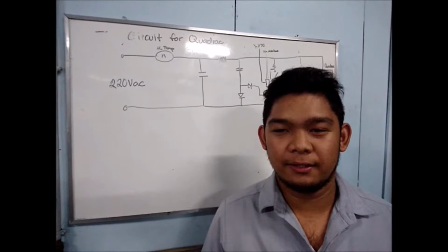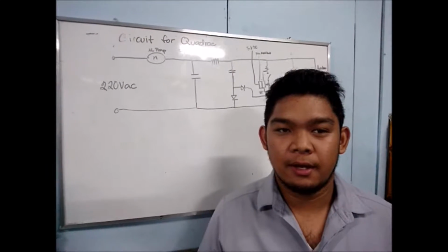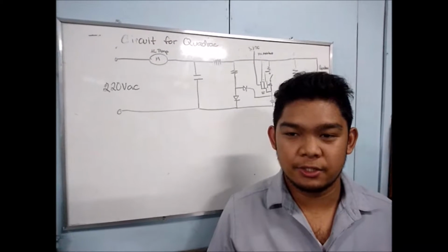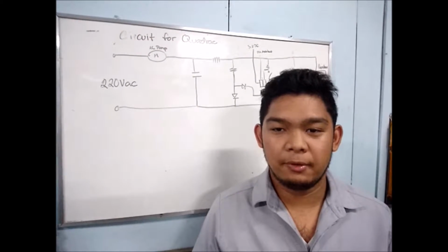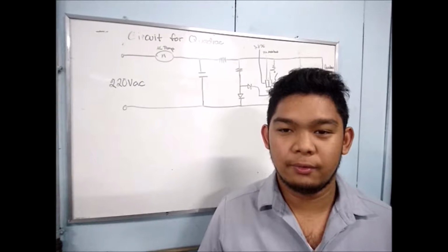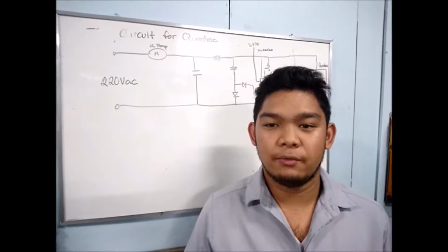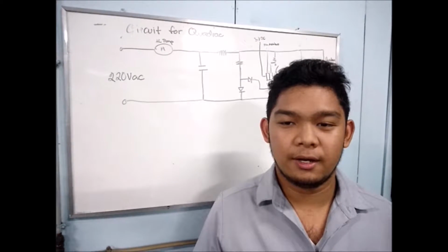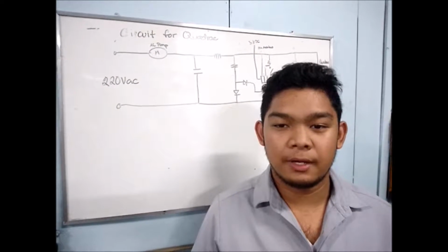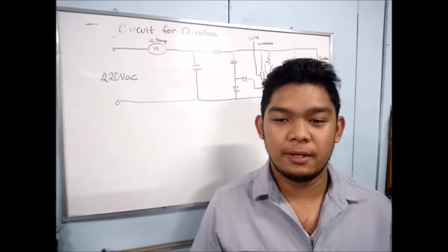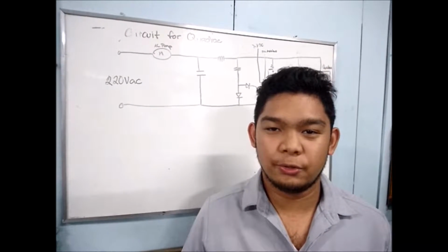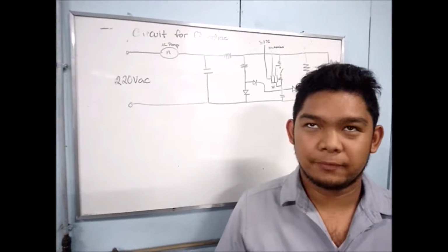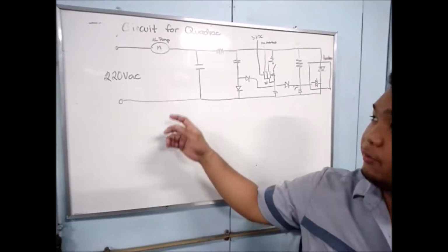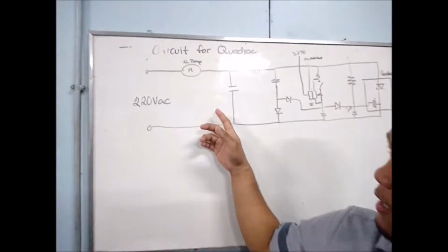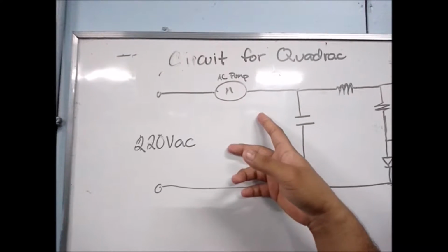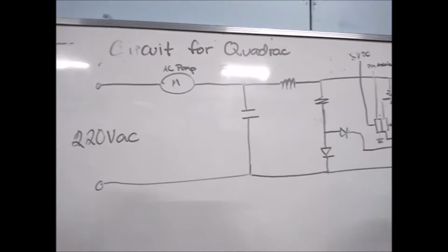I am to explain the manipulated variable and control system. The manipulated variable in the researcher's project is the flow rate of water coming from the cooling tower. The water will flow through the heat exchanger system, which serves the purpose of cooling air before going to the accumulator tank. The control system the researchers will be using is a Quadrac unit combined with its circuit. As you can see here, the AC pump is connected to the circuit created for the Quadrac.